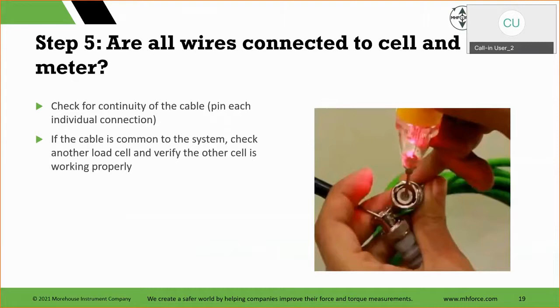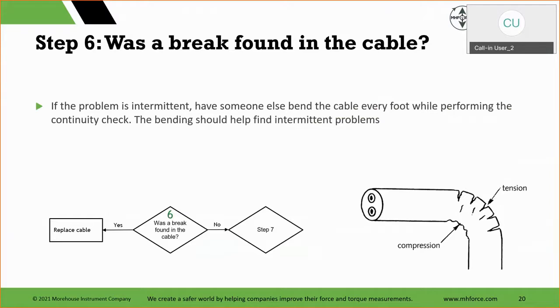And what we do here is we check for continuity, because sometimes you see a ding in the cable, like indented, and you don't really know what that is. So by checking for continuity, often this is easier with two people. You pin one side to the other, and then you have somebody bend it. And if it's intermittent, here you can see the tension and compression on the cable. Have someone bend it every foot. If your signal breaks, this is where I like to put the meter in diode test, which sends some small voltage and the meter beeps at you. So as long as you have continuity, the meter beeps.